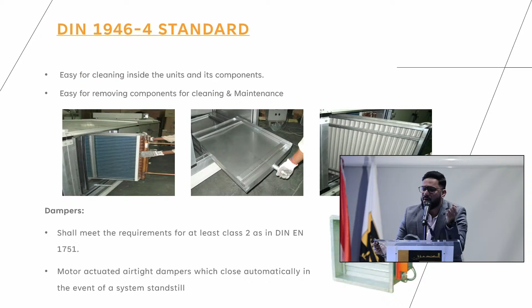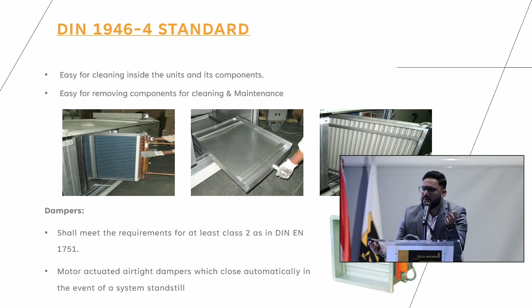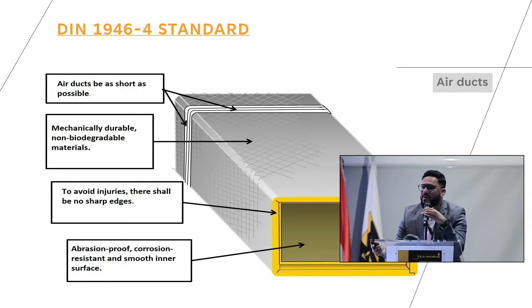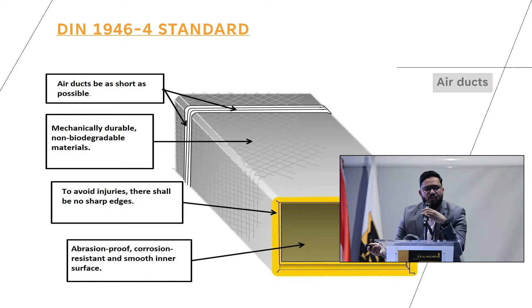Second, the air handling unit itself shall always be designed with a supply and a return or fresh air damper, where when the unit is not in operation, the dampers are fully closed and no contamination happens in the air handling unit itself. The ducts, as defined in the DIN 1946 standards, should be as short as possible so that no more contamination is carried along. There should not be any sharp edges in the duct, and it should have abrasion-proof, smooth inner surfaces.